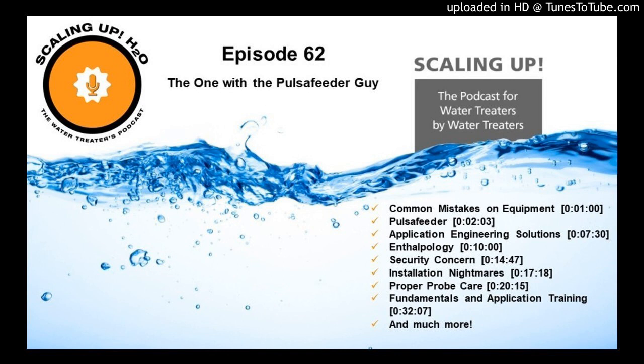So the demand on a probe in that application, let's factor out the fact that it sits in a 100-degree car for a couple hours out of the day, but the fact that it's not subjected to flow 24/7 helps it a lot. So think about this probe. It's in the process, actively reading almost 24/7. Things get on it. Oils cover the probe. As I mentioned, that buffer depletes over time.